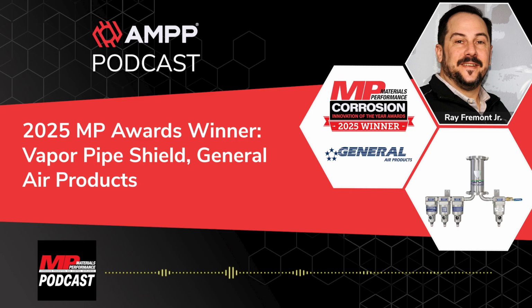We did testing on the effectiveness of VPCIs, the specific Cortec product we're using, and also the migration of that product through the system, which allowed us to figure out how much of the VPCI product we needed with our vapor pipe shield unit, in conjunction with the size of the system, the amount of time we wanted the corrosion mitigation to take effect, and the airflow of our air compressors. We had to weigh and measure all of those factors until we zeroed in on a product line, which took another year or two.